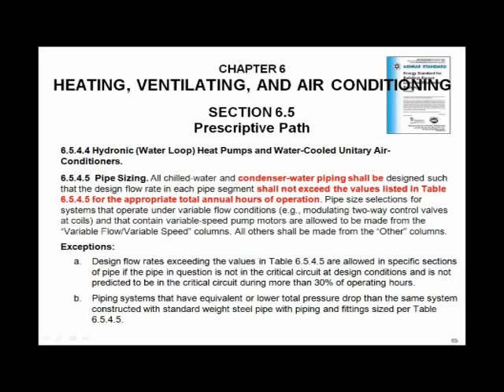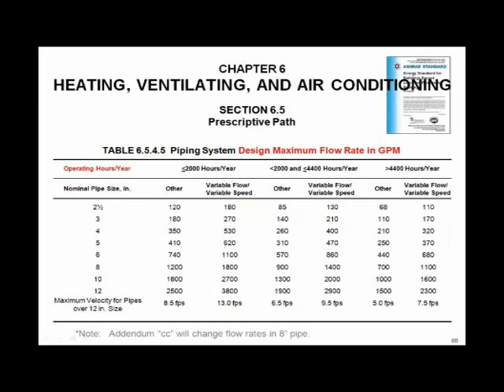I'm telling you there's a table now for sizing pipe based on the hours of operation. Here's the table. Brand new. Most engineers aren't aware of this yet. And it's already in the code, so you need to start being familiar with this. How will your firm, how will you deal with the code's requirement for minimum pipe sizes? And take note, the first column is based on 2,000 hours or less, other or variable flow. Other would pretty much be constant flow. Variable flow is what we speak of, obviously.